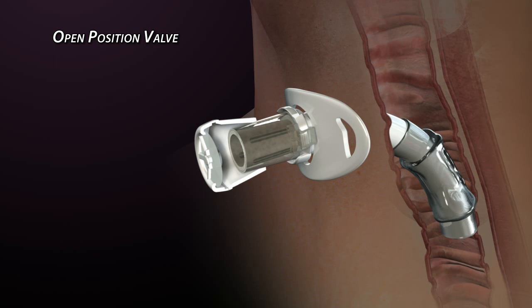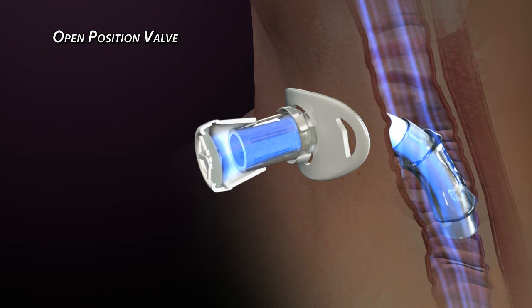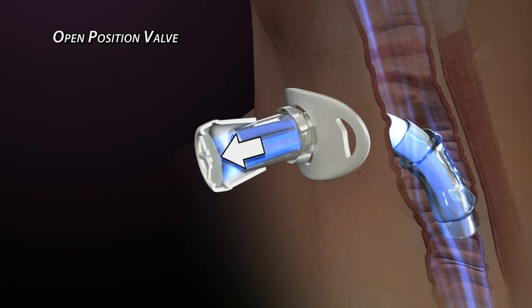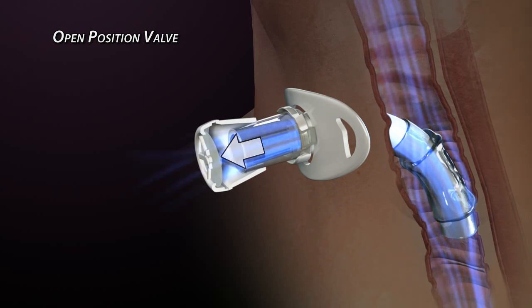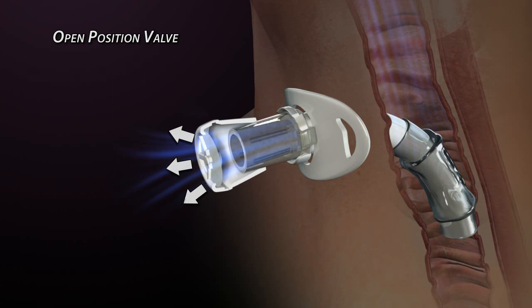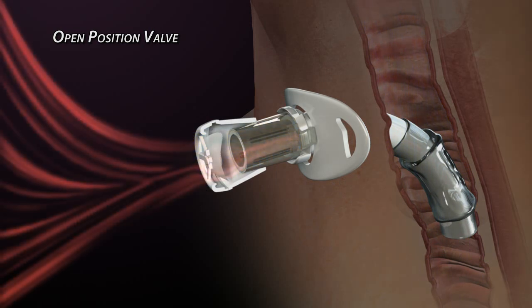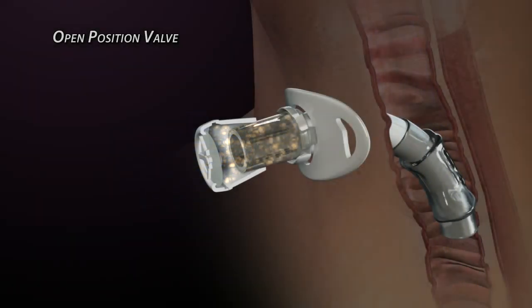At this point, the valve is not actually closed. Reversed airflow, which is produced by exhaling, is necessary to force the membrane against the valve body to produce a seal. Before the membrane actually closes, there is a short time-lapse where some exhaled air can escape. In addition, some common breathing patterns create an airflow phenomenon that can cause the membrane to vibrate or oscillate, which prevents it from completely sealing, resulting in noise as air leaks out. The open position valve also allows secretions to travel up the tracheostomy tube and potentially occlude the tracheostomy tube and the valve.